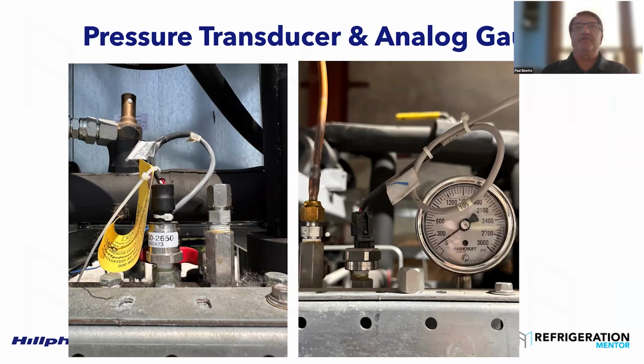You've tested your oil switches before you put oil in, and turn your breakers off. Turn on your control circuits. Let your oil switches go through their time sequences and trip. You want to see that they're tripping. Your wiring is good. You want to make sure your HPV valve is calibrated. Your bypass valve is calibrated. Calibrate it per the control manufacturer's recommended steps to do that.